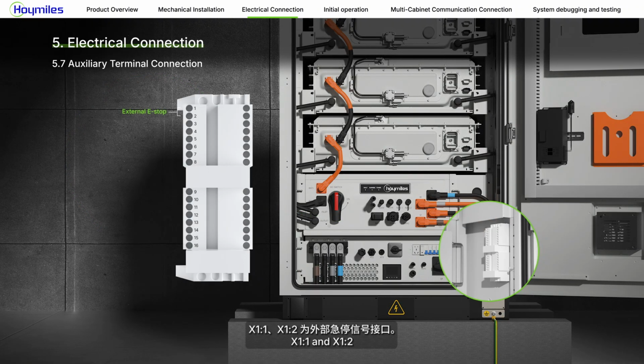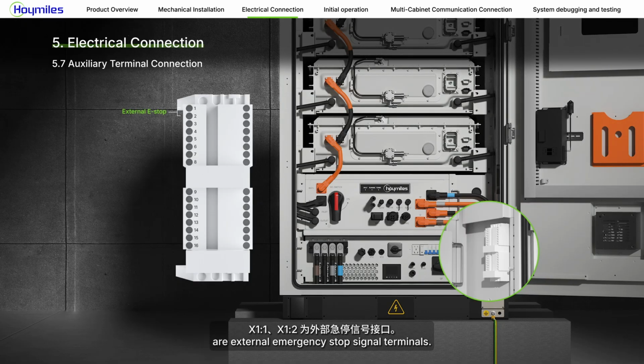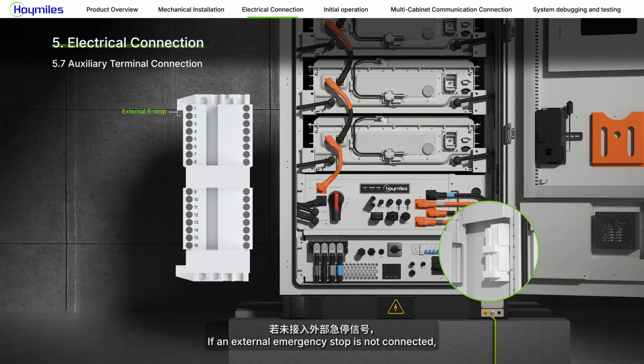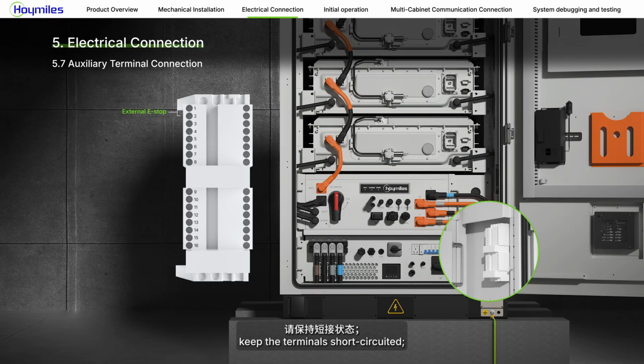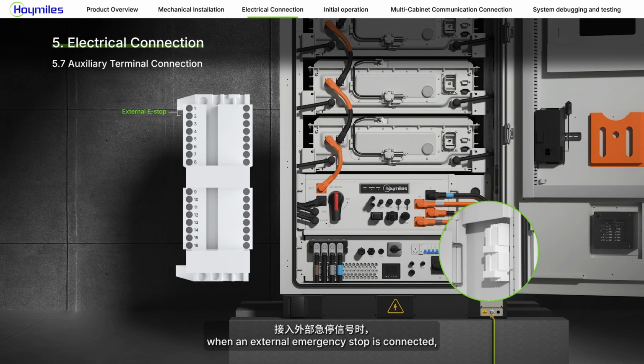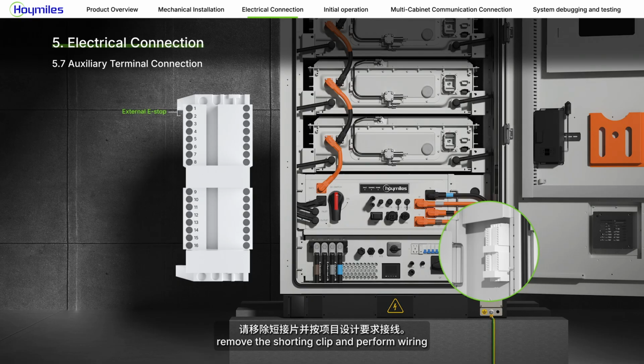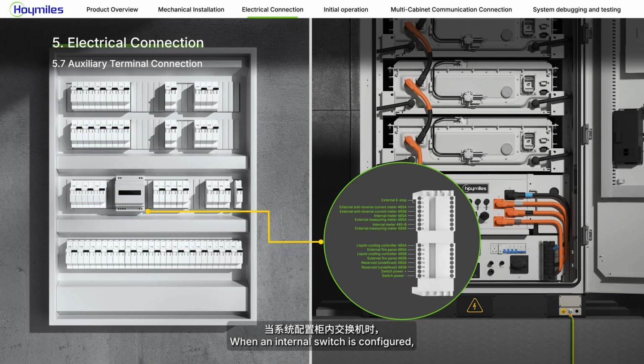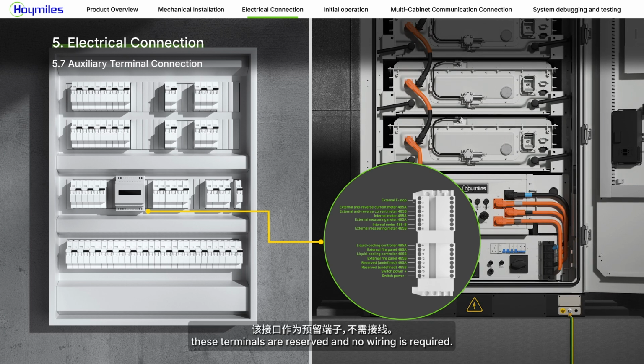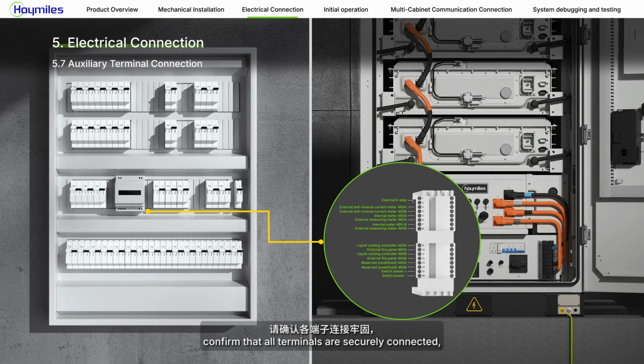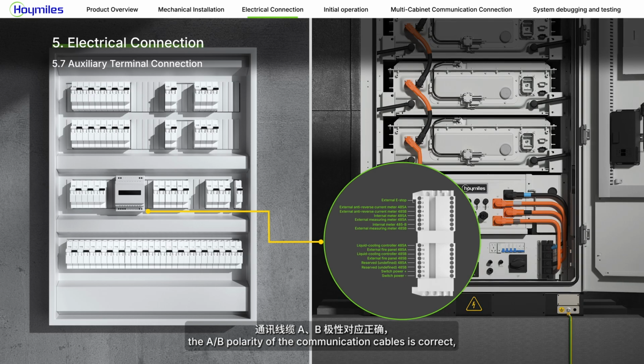X1:1 and X1:2 are external emergency stop signal terminals. If an external emergency stop is not connected, keep the terminals short-circuited. When an external emergency stop is connected, remove the shorting clip and perform wiring according to the project design requirements. When an internal switch is configured, these terminals are pre-connected. When no internal switch is configured, these terminals are reserved and no wiring is required. After wiring is completed, confirm that all terminals are securely connected, the A or B polarity of the communication cables is correct, and there is no looseness or poor contact.